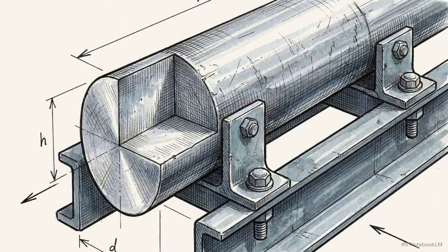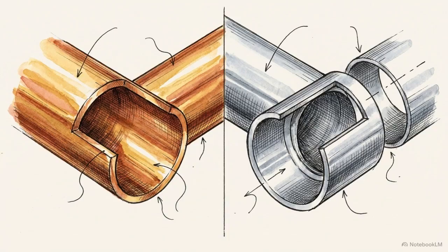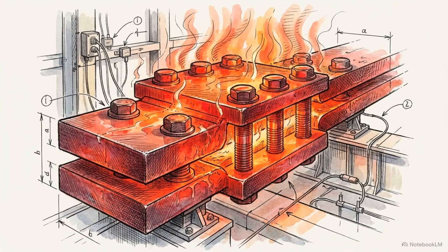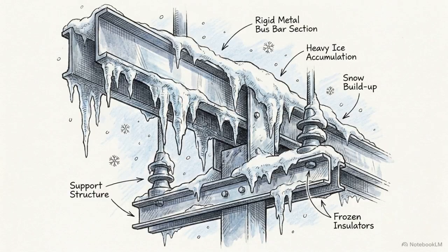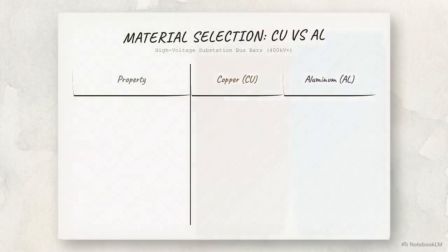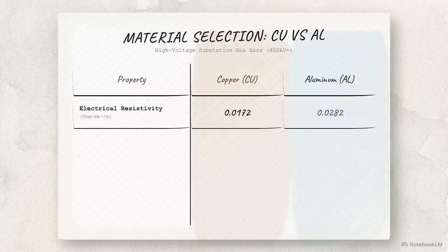Moving from theoretical topology to physical construction reveals another layer of complexity. These architectures must be built from hundreds of tons of highly conductive metal. Engineers evaluate copper and aluminum against strict requirements. The metal must have low electrical resistivity, a high softening temperature to survive thermal spikes, and strong mechanical properties to withstand outdoor environments. This comparative data table shows copper holding a distinct technical advantage.